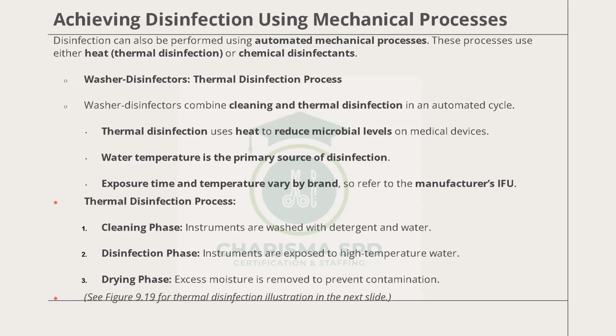Washer disinfectors have a thermal disinfection. In fact, the washers that we have, during the rinsing stage, the temperature, some machines, Steris Amsco machines, normally get to 192 degrees Fahrenheit. But Getinge machines sometimes get to about 205 degrees Fahrenheit. Now, at that point, we call it thermal disinfection.